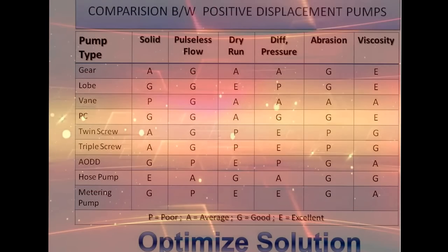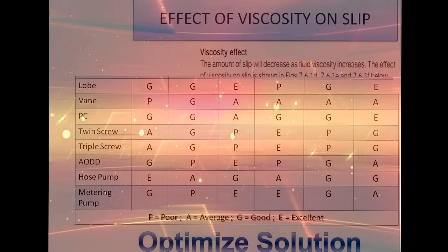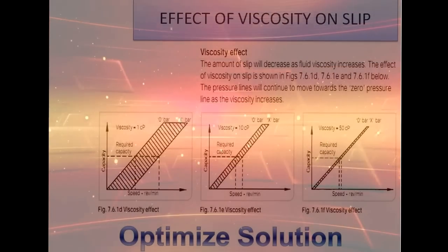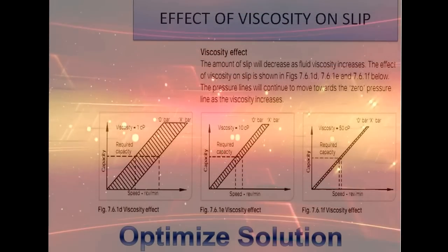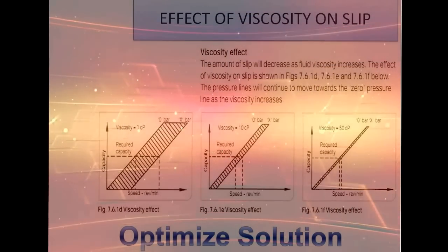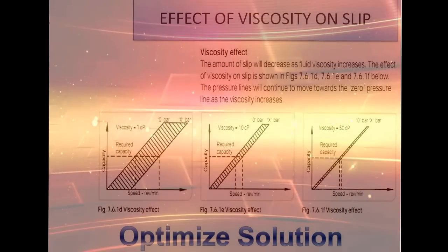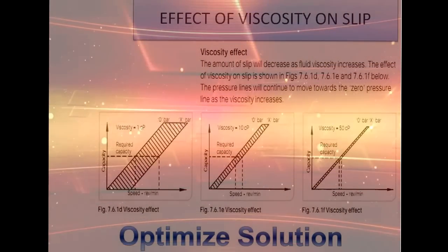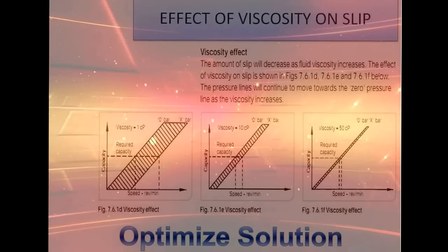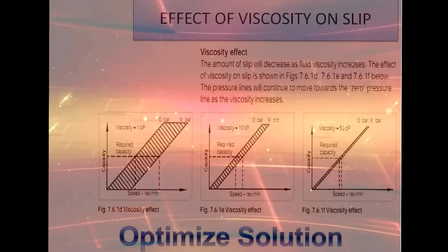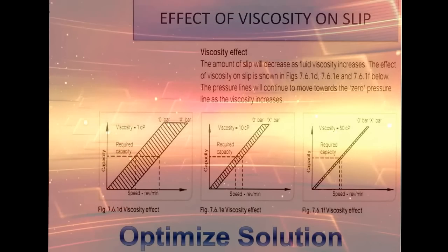Can anyone tell me what slip is in PD pumps? What percent of slip is expected in a rotary pump? While working under high differential pressure, some amount of liquid moves from the discharge side of the pump towards the suction side through the clearance between the casing and rotor.